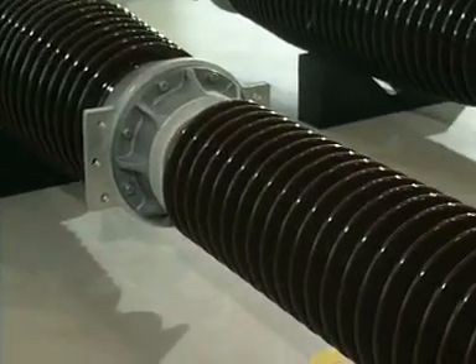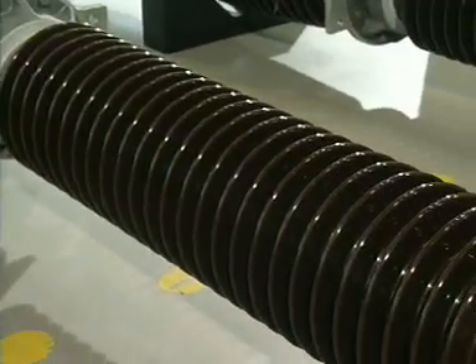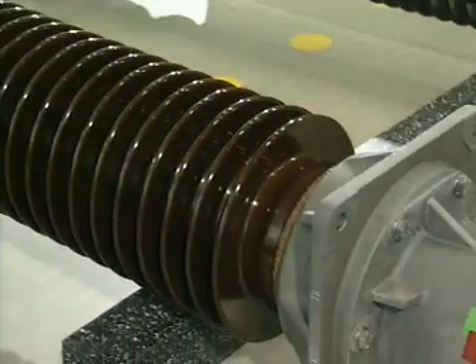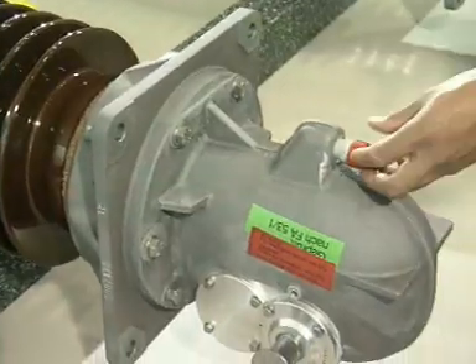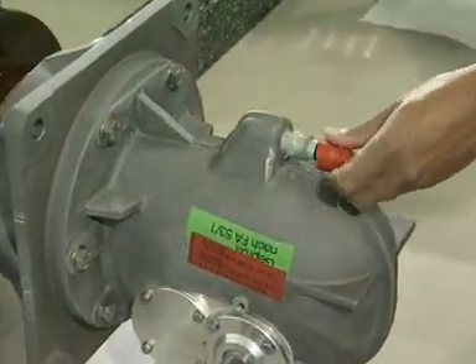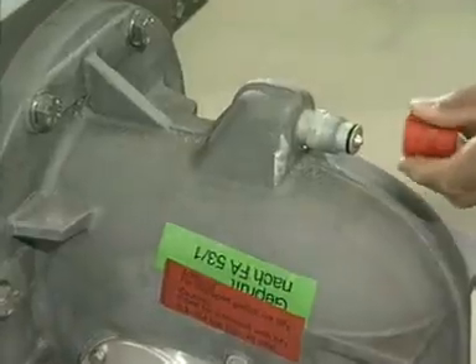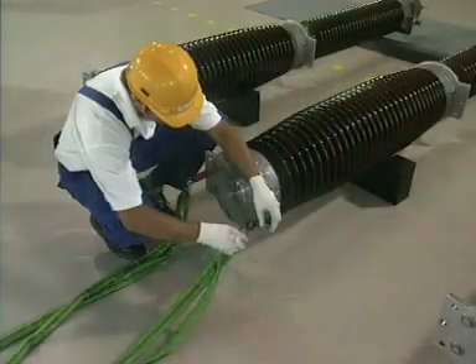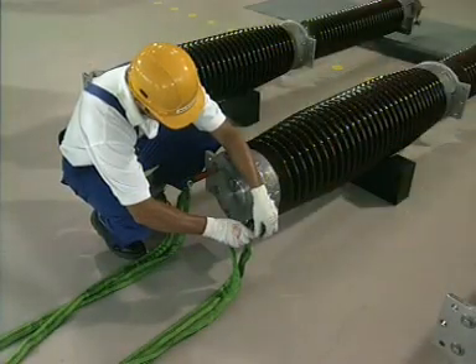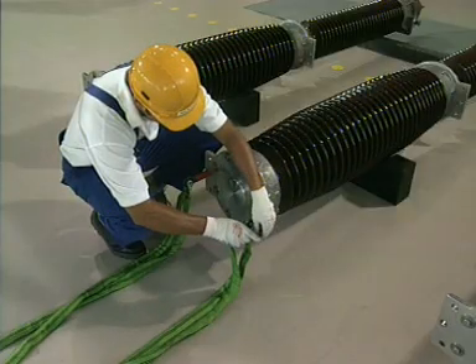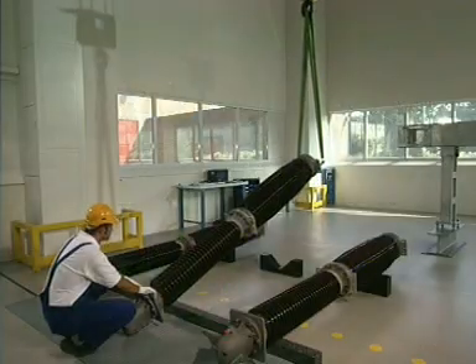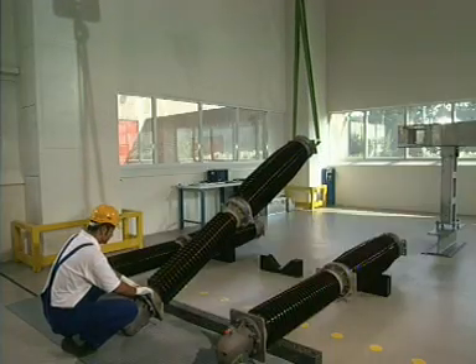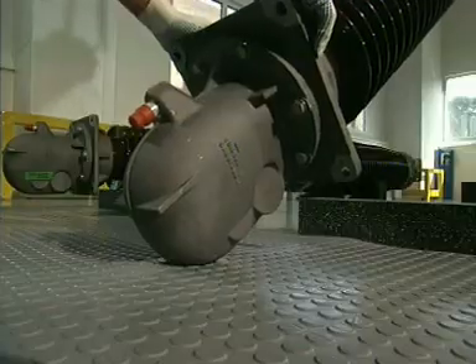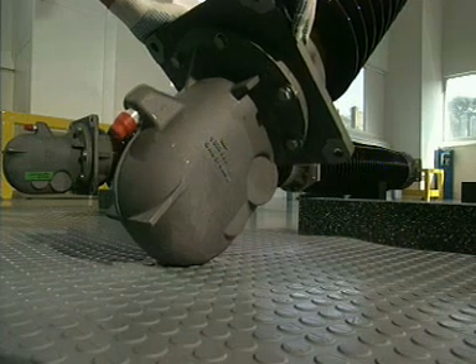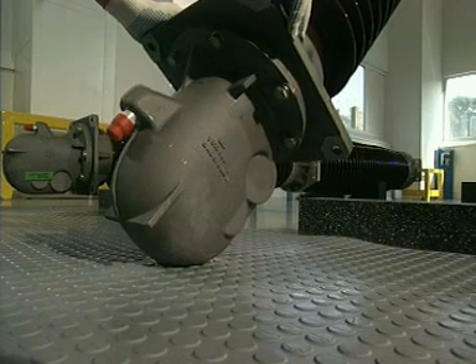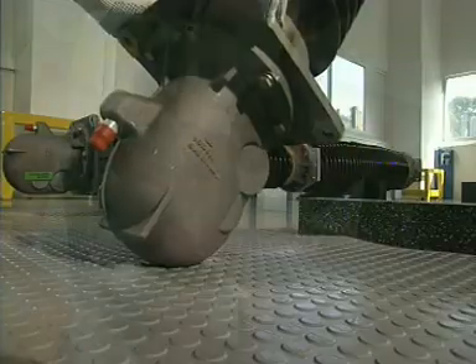Inspect the new pole columns visually and check the SF6 shipping pressure by pressing the valve mushroom of the coupling. Gas escape must be audible. Attach rope loops to the upper connection surfaces of the new pole column. Slowly pull the pole column to an upright position, making sure that the crankcase rolls down over the cast seam. This prevents damage to the gas supply connection and torque shaft.